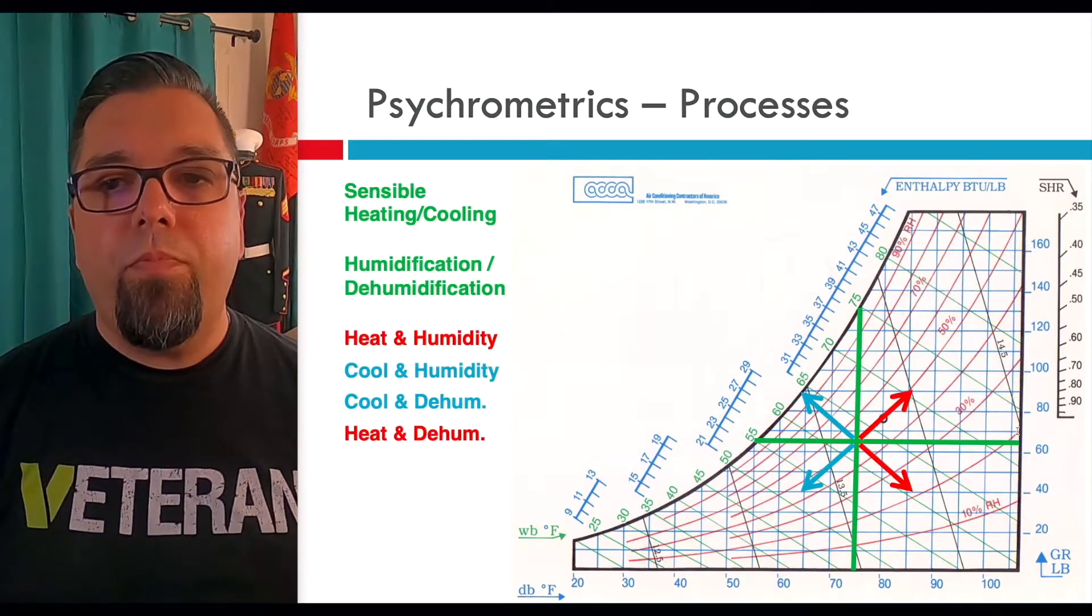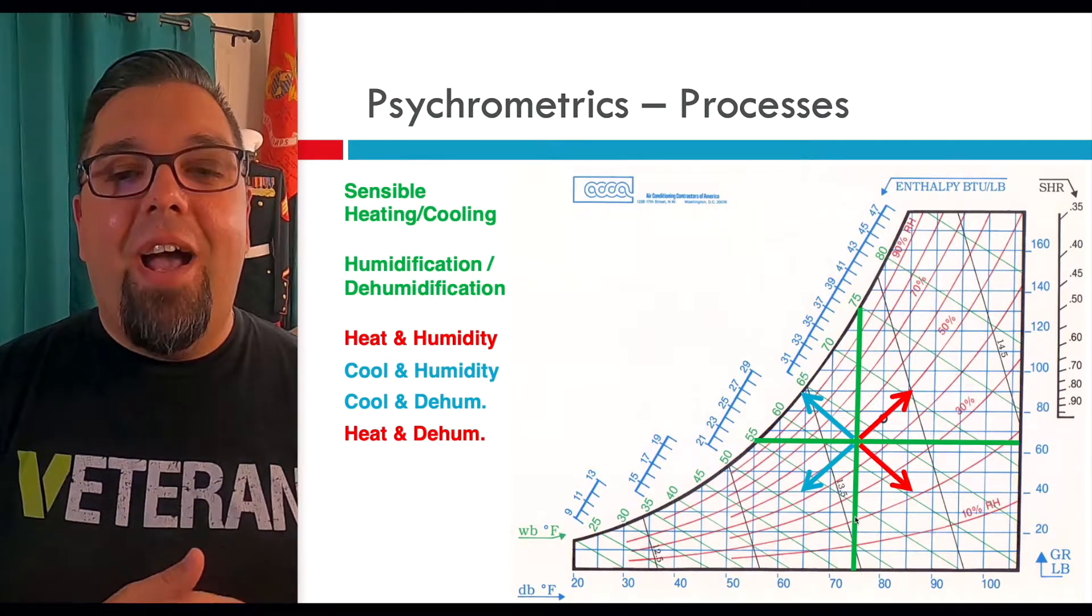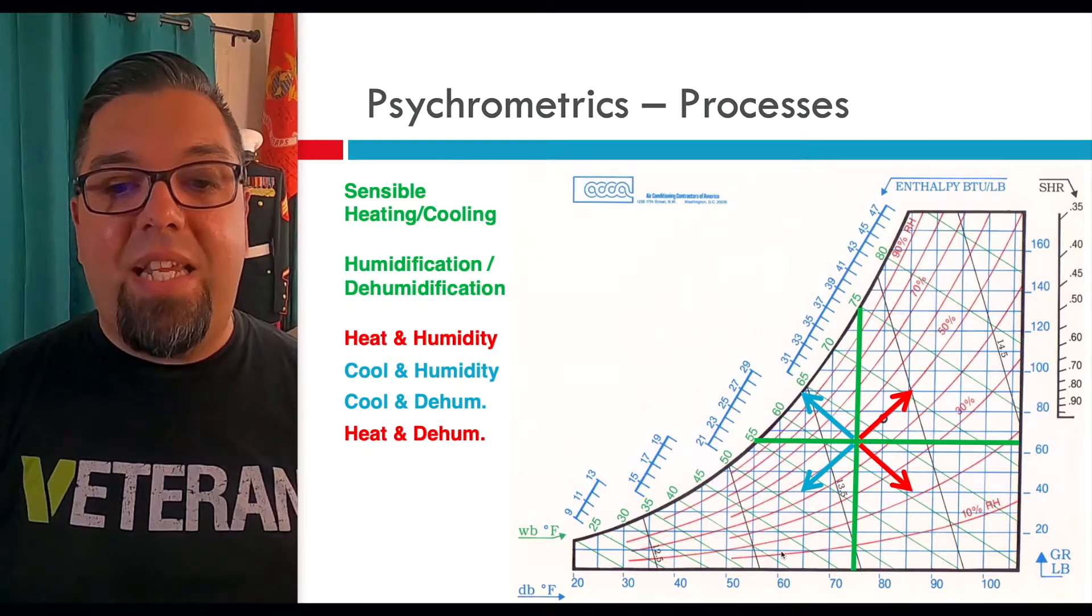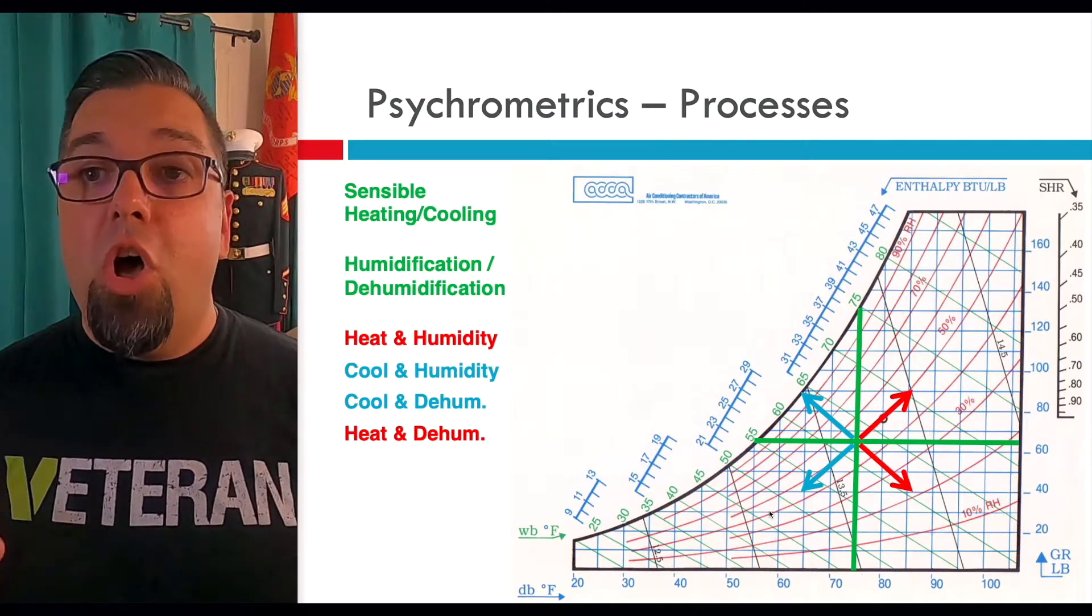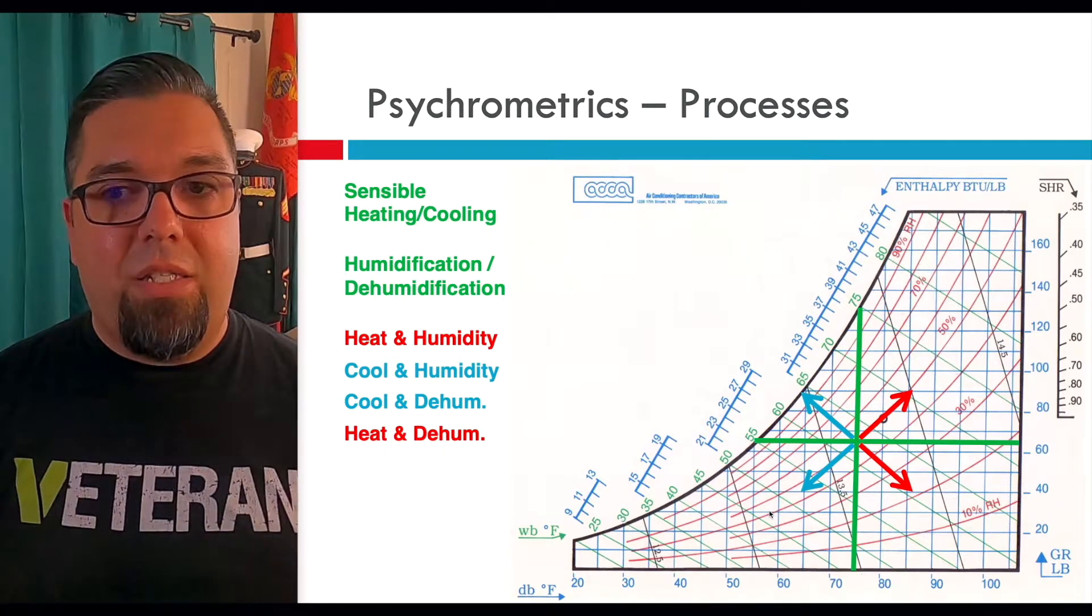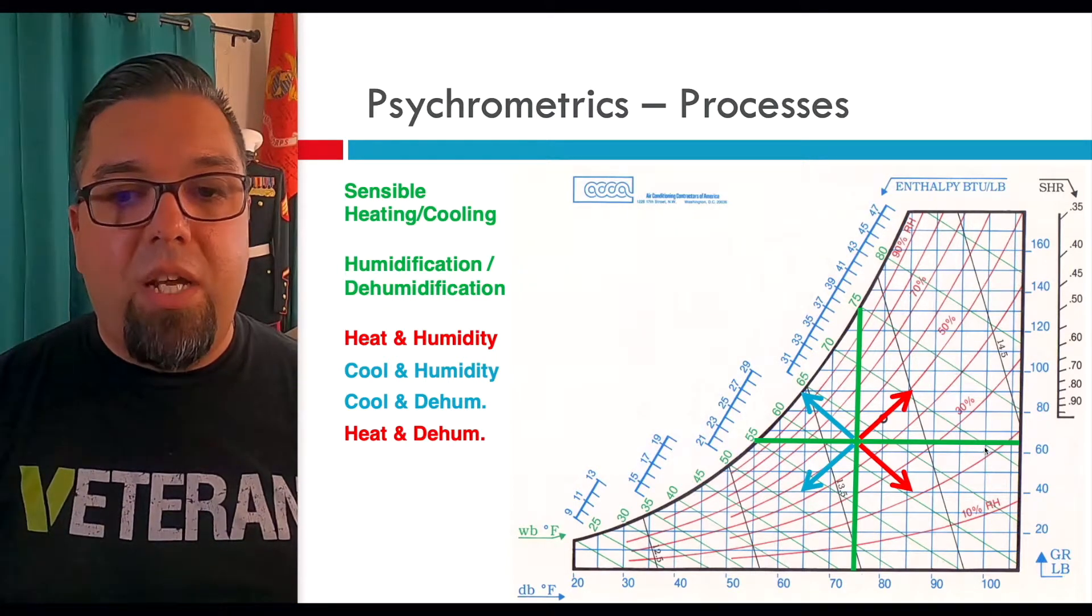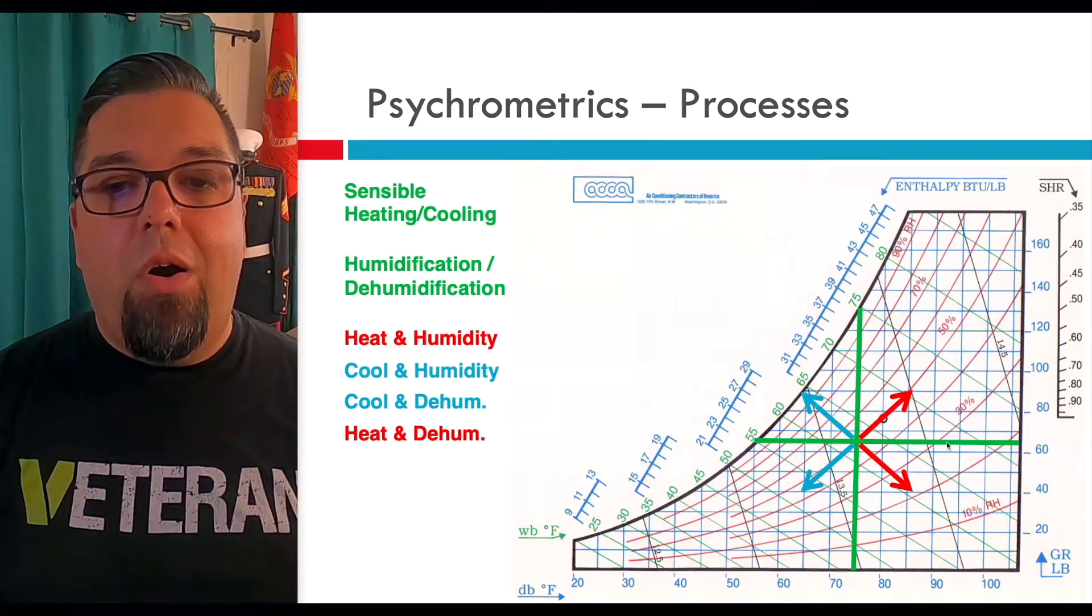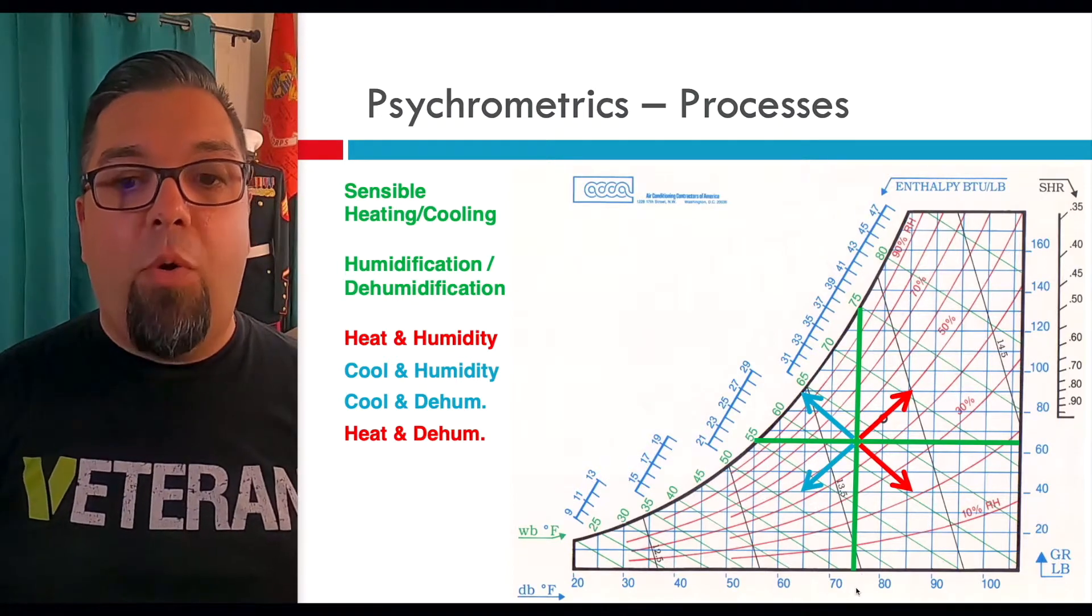That's how to read the chart. Now I'm going to talk about what the chart can do for you. If we have a horizontal line we're going to be changing sensible temperature. We could start out at let's say 60 degree dry bulb in the return of a furnace and if I was to not add any humidity or not remove any humidity, a horizontal line will show sensible temperature being added to the space if we're going to move to the right. If I stick my probe in the supply of the furnace and it's a hundred degrees coming out, you can see that would move horizontally. We're not adding any humidity, we're just changing sensible temperature.